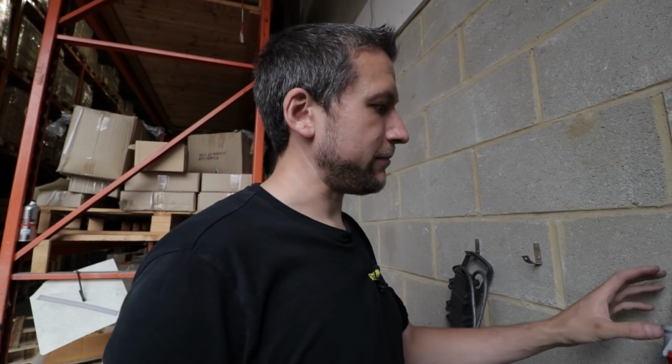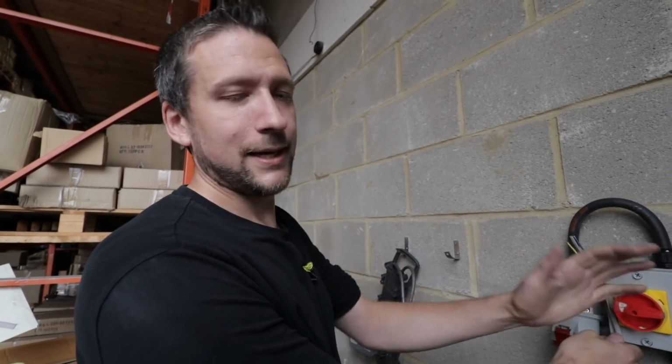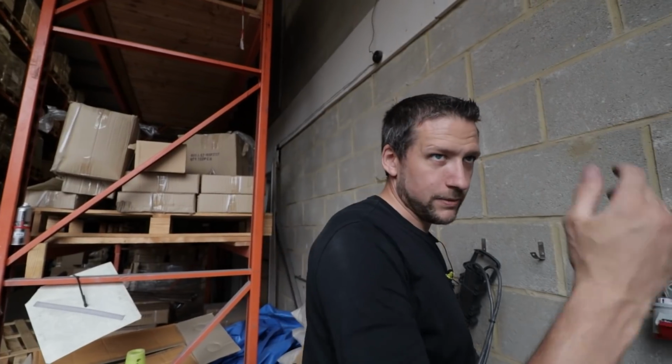While I was talking to James, in his previous company this was how they got around it. Because 3-phase RCDs are so expensive, they ditched that. They just put a stuffing gland on and hardwired it in, and that way they get around the whole RCD cost issue. I'd just rather have an RCD. The client pays the bill anyway, so it just makes sense to do it.